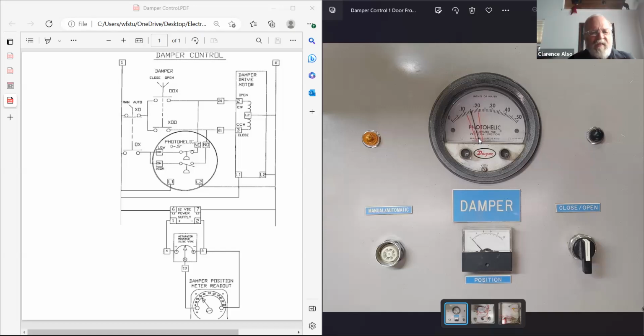What kind of things are possible there? I mean, all this here does is supply 110 volts to it, it's these things right here that aren't tripping. So what else do we have in common with this? This is an electronic pressure switch that you have here, and it needs power too, in order to get these things here to move. So what is in common with that photohelic there that is affecting these switches from not operating? That's what's happening, they're not operating.